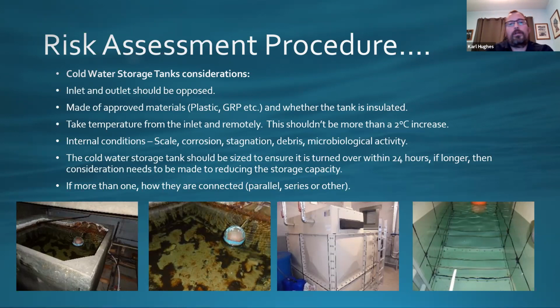You've got to make sure that the cold water storage tank is sized appropriately. You need to make sure that the water within the system is turned over within 24 hours. If it's longer, then you need to consider whether you need to reduce the capacity within the tank or change it to a smaller tank to get that flow of water through. That one on the left-hand side at the bottom, for example, when I did more digging, is a 2,000 litre cold water storage tank that fed 2 toilet flushes in a building. That was it. So the first thing you would say there, straight away on the risk assessment, is just get rid of it, bypass it to mains.